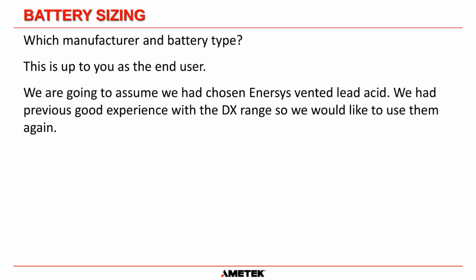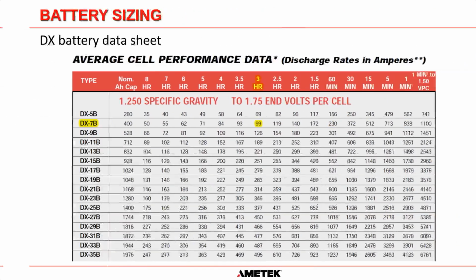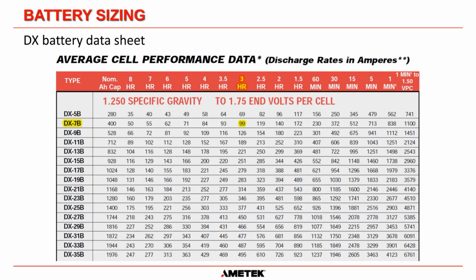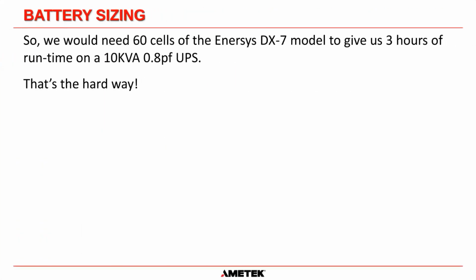So we're going to say we had a previous good experience with the DX range, and we would like to use them again. So we would go to the Enersys DX datasheet, and we would look up the table, and we'd find that for the 3 hour rate, we need a value above 86.6 amps. So the DX5 is not good enough. It's only going to give us 69 amps. But the DX7 will give us 99 amps, which is above 86.6. So that is good. So we can say, okay, the DX7 will fulfill our needs. It will do 3 hours at 86.6 amps. So we are good.